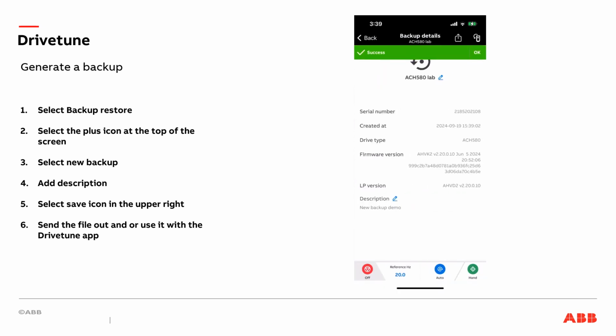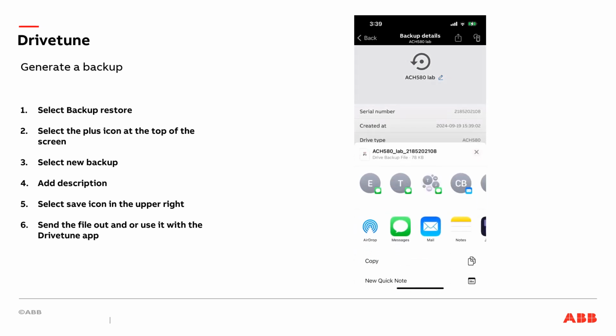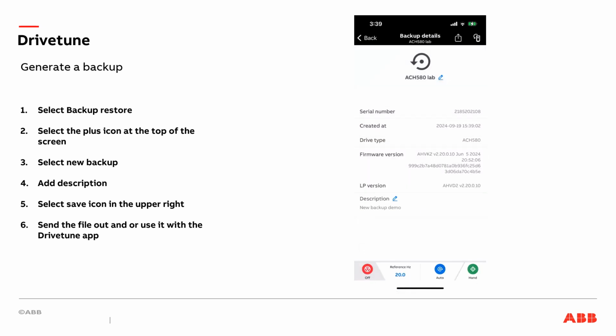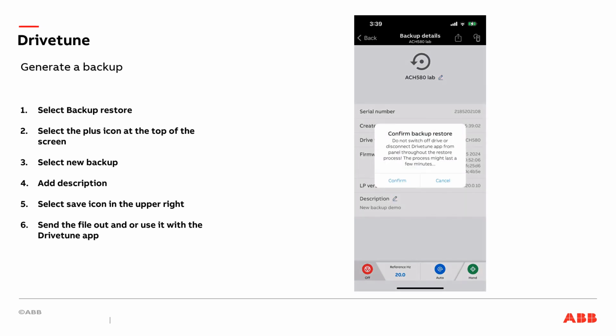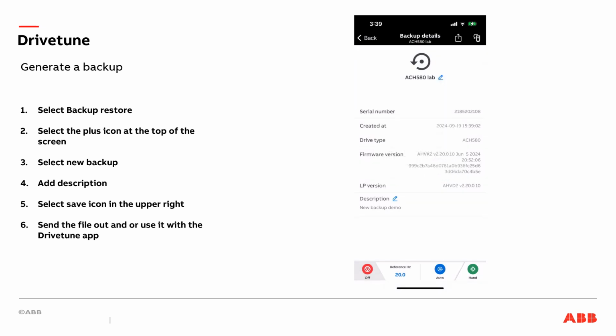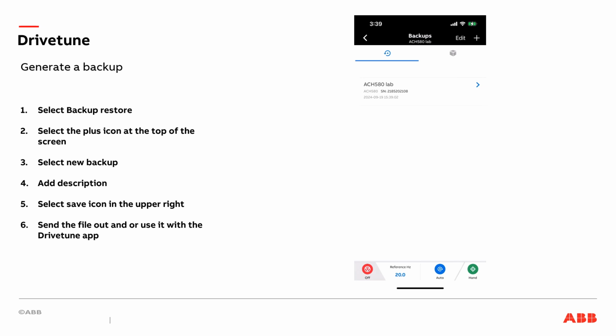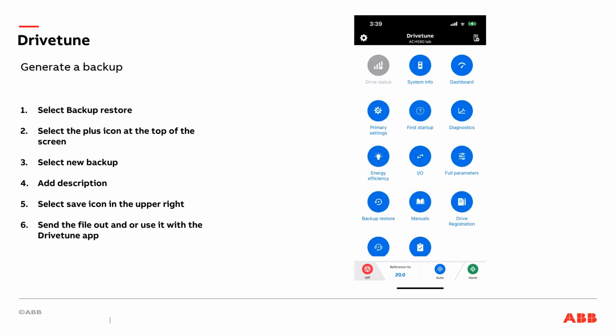When it is completed, you will get a green OK displayed on the screen. The resulting file has reference data including serial number, firmware, and file creation date. You'll also notice that in the upper right-hand corner there are 2 options. You can send this file out through mobile device communication apps such as text or email, or you can select the ability to load that backup file into another drive. A backup can be saved on Drivetune in that device and used to program other drives that are similar in frame size and application.